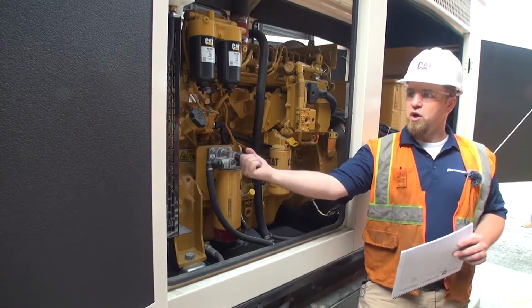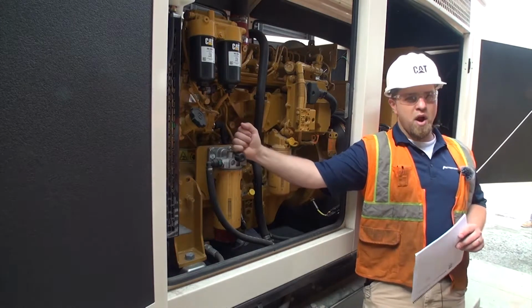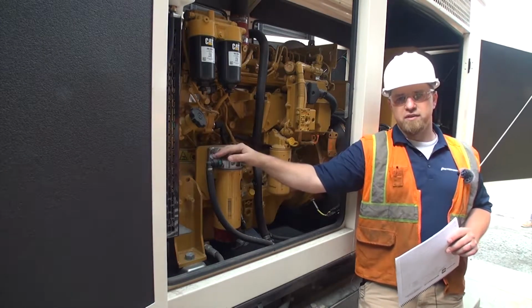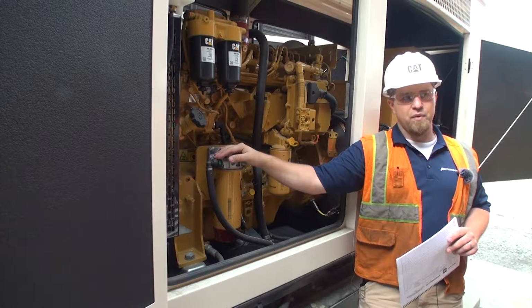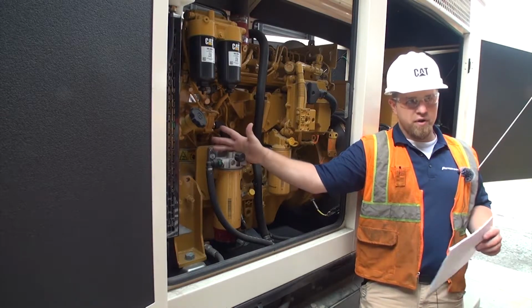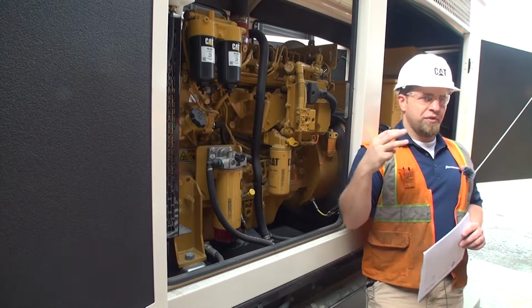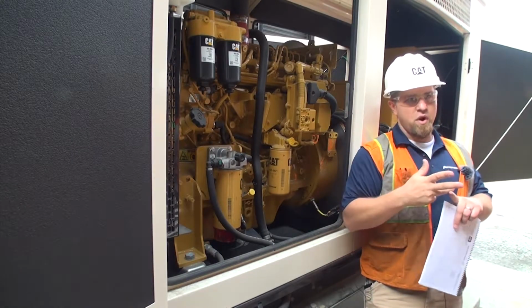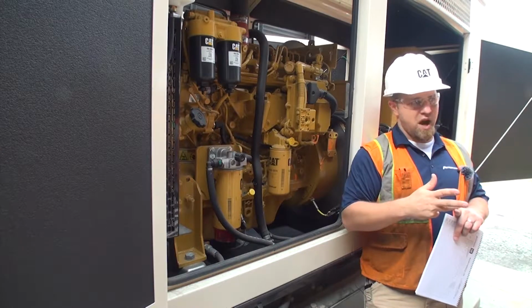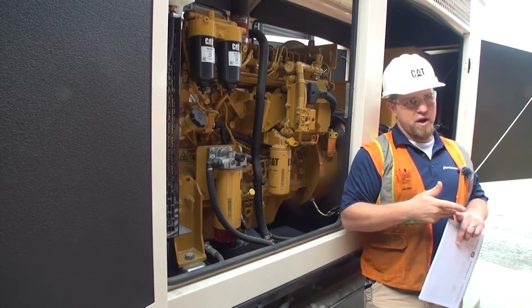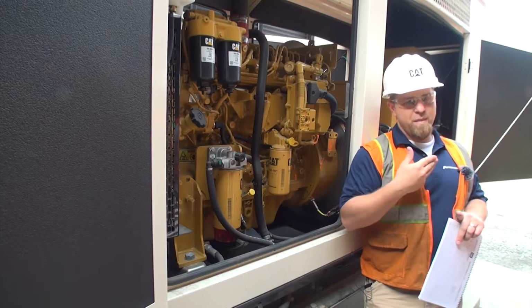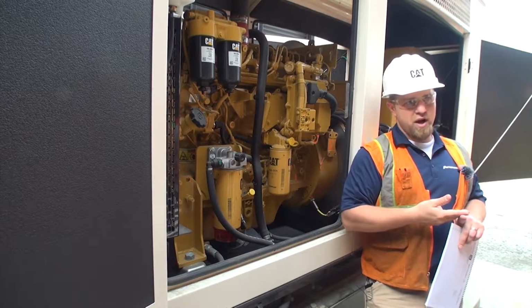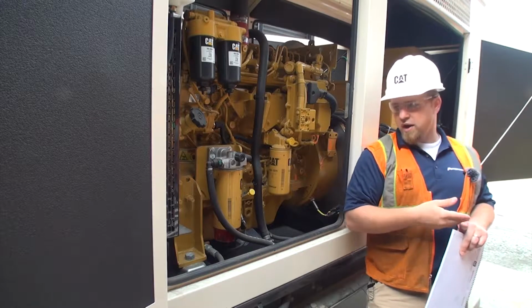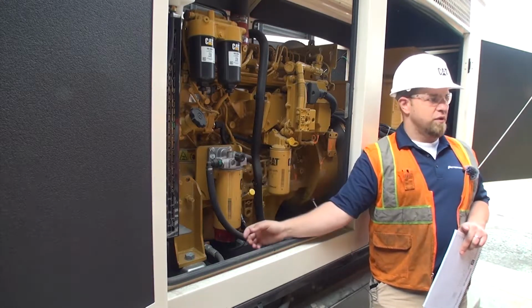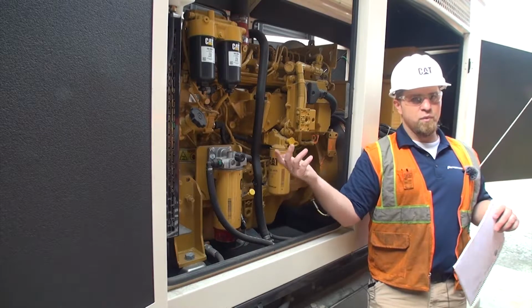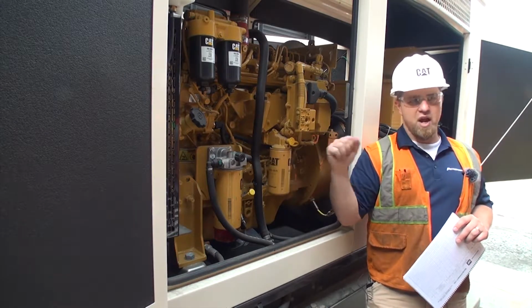Make sure the hand primer's closed. The reason I keep pointing out the hand primer is for two reasons. One, this is your usual best way to get it back up and running. So if you come out here and there's an overcrank alarm, that means it went through 3 cycles. This thing's going to try and run 3 times. Crank, crank, crank, stop, rest, crank, crank, crank, stop, rest, and then go again. So if you've made it through all 3 and it says overcrank, not started overcrank, then this is where I'd be going to see if you lost your prime. Because really that's one of the main reasons you're going to have an overcrank, is just not getting fuel.